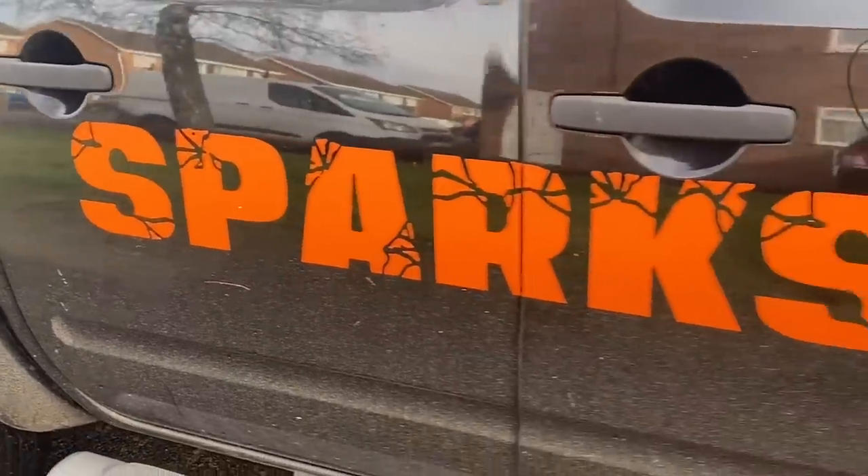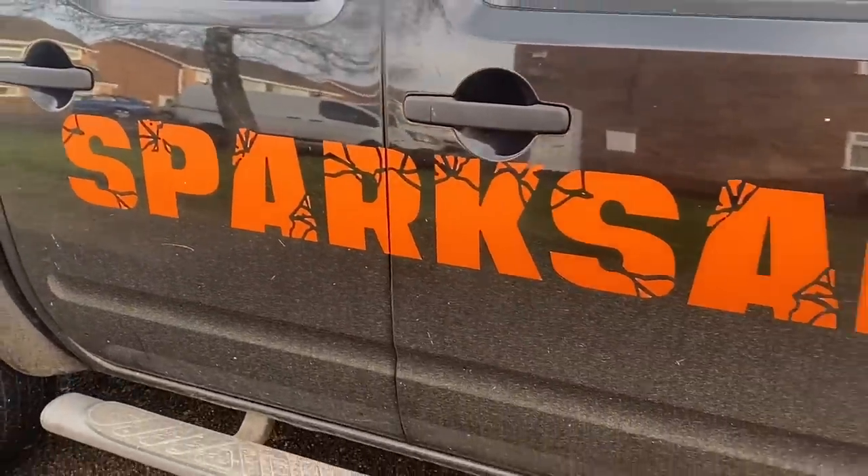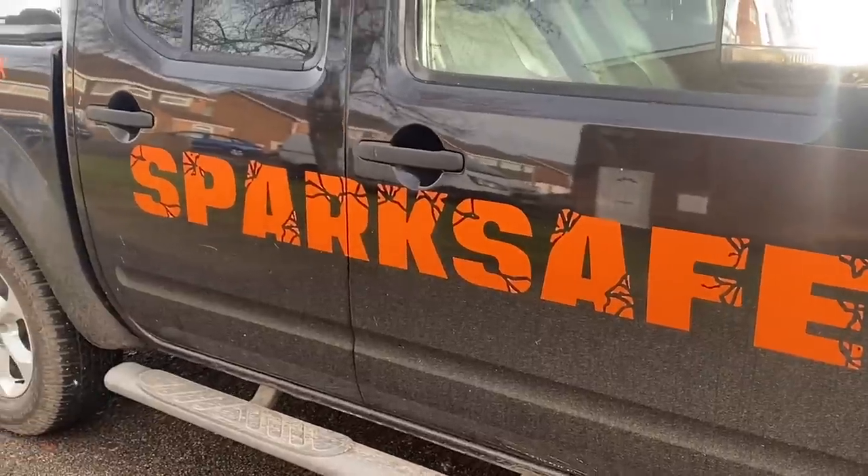If you'd signed all elements of that certificate and there was an issue in the future, that's going to be your problem. Luckily I saw it at that stage and said to who I deal with, that's something I'm going to have to change. It was only a radial socket circuit feeding just this room where the polystyrene had been put in. It was quite an easy change — just had to rewire it. And the builder actually took the polystyrene off completely because they wanted to target the damp in a different way and get a damp expert in.